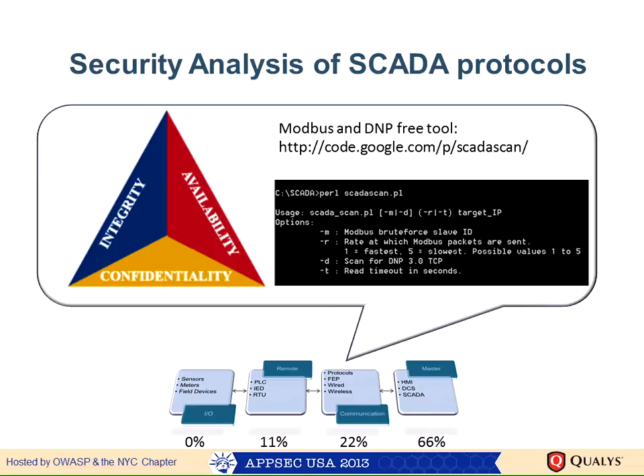Many SCADA security protocols were not developed with security in mind. There is basically no confidentiality, integrity, or availability built into the protocol. For example, if you use Modbus to tell the server to lower the temperature of a connected device, it will just do it — no credentials asked, no authorization check. These things are not built into SCADA protocols because they were designed 30 years ago for closed environments.